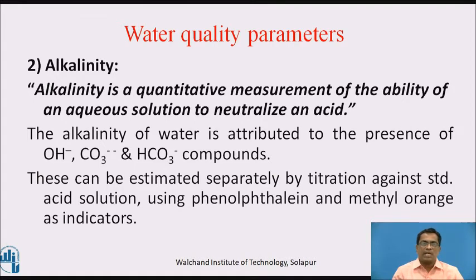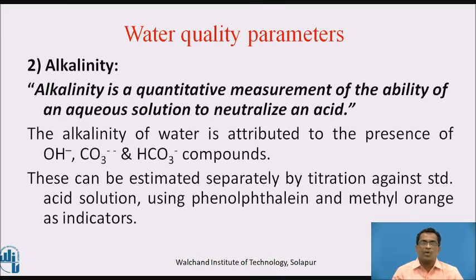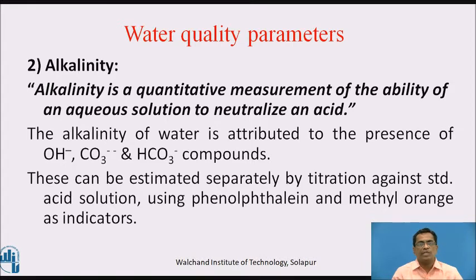Second water quality parameter: alkalinity. Alkalinity is a quantitative measurement of the ability of an aqueous solution to neutralize acid. The alkalinity of water is attributed to the presence of hydroxide ions, carbonates, and bicarbonate compounds. This can be estimated separately by titration against standard acid solution using phenolphthalein and methyl orange indicators.